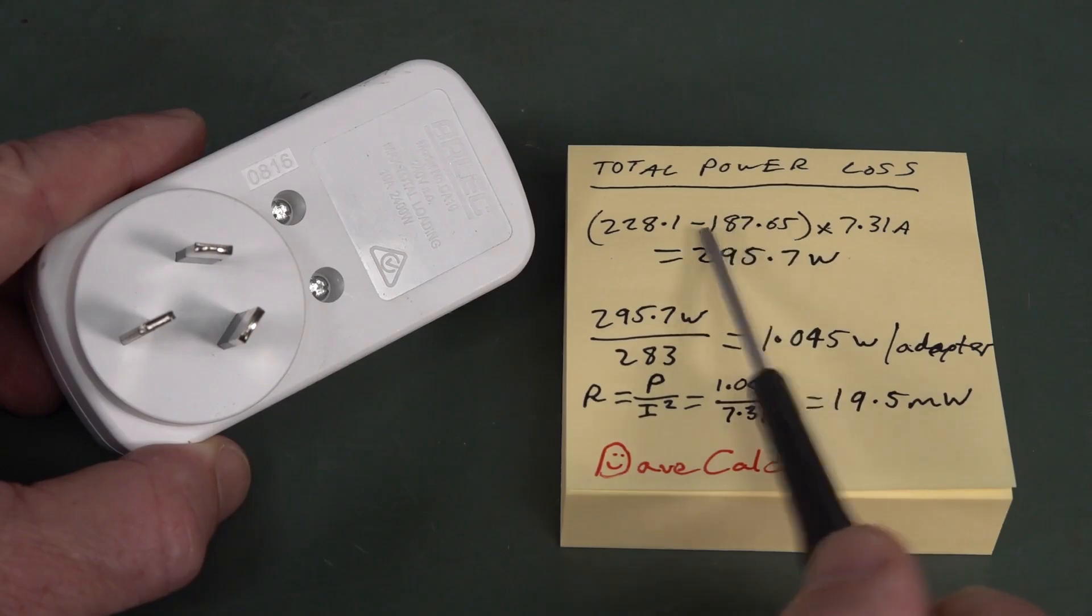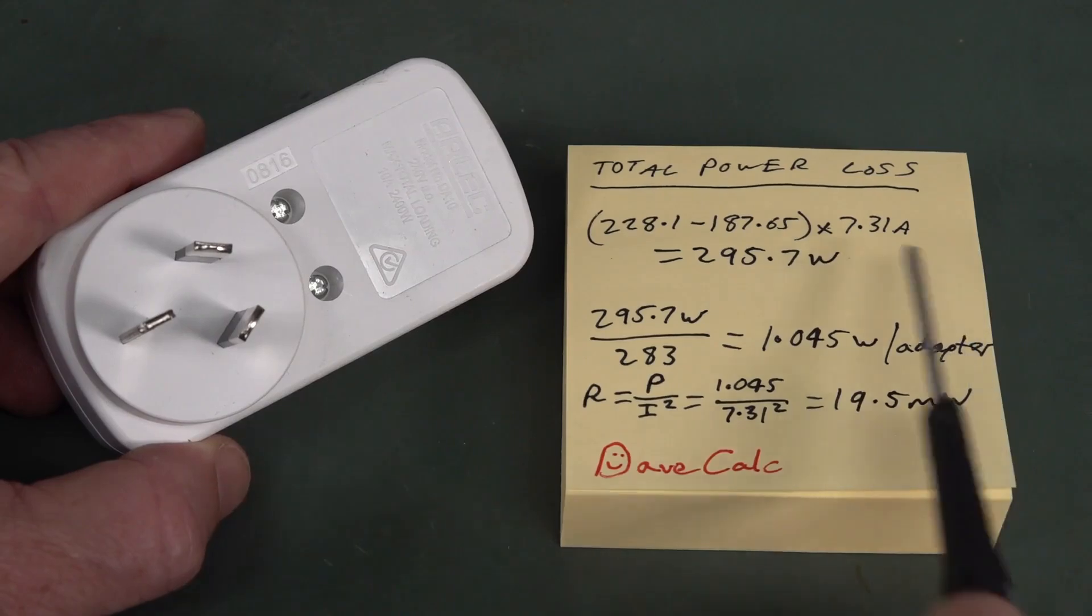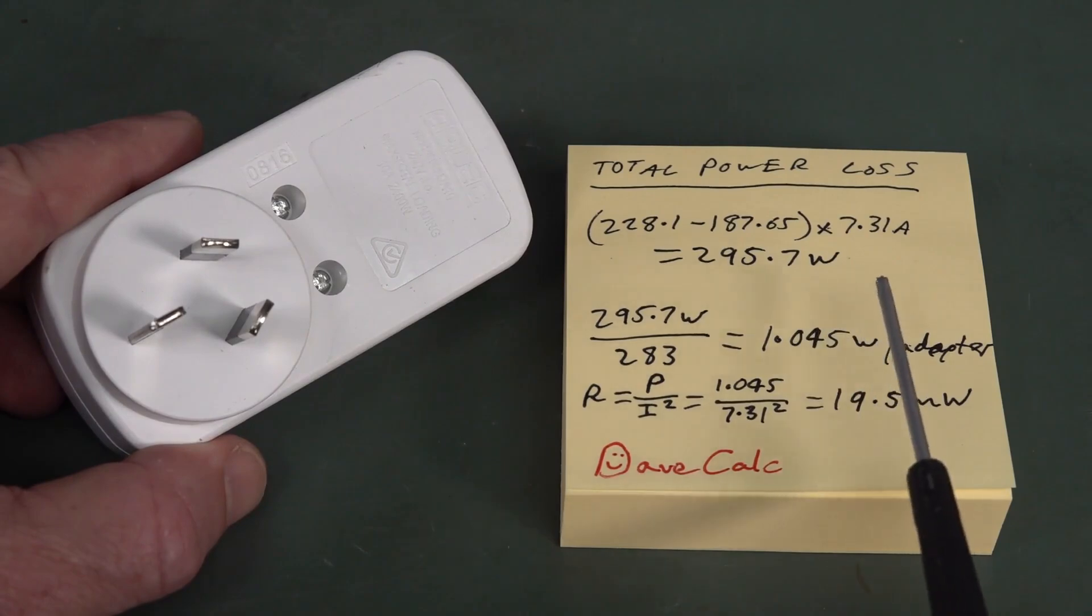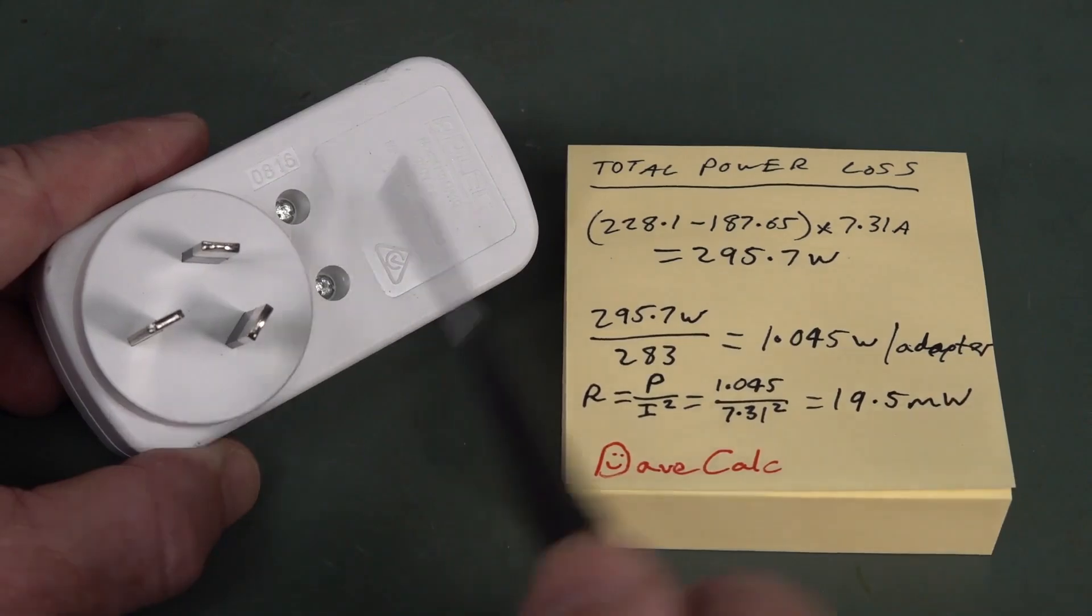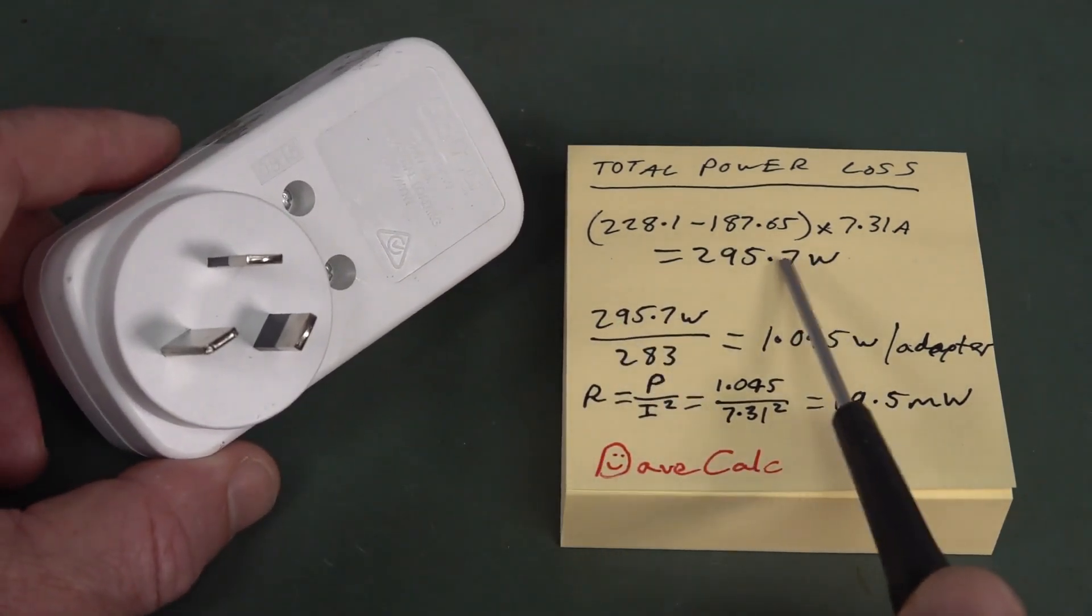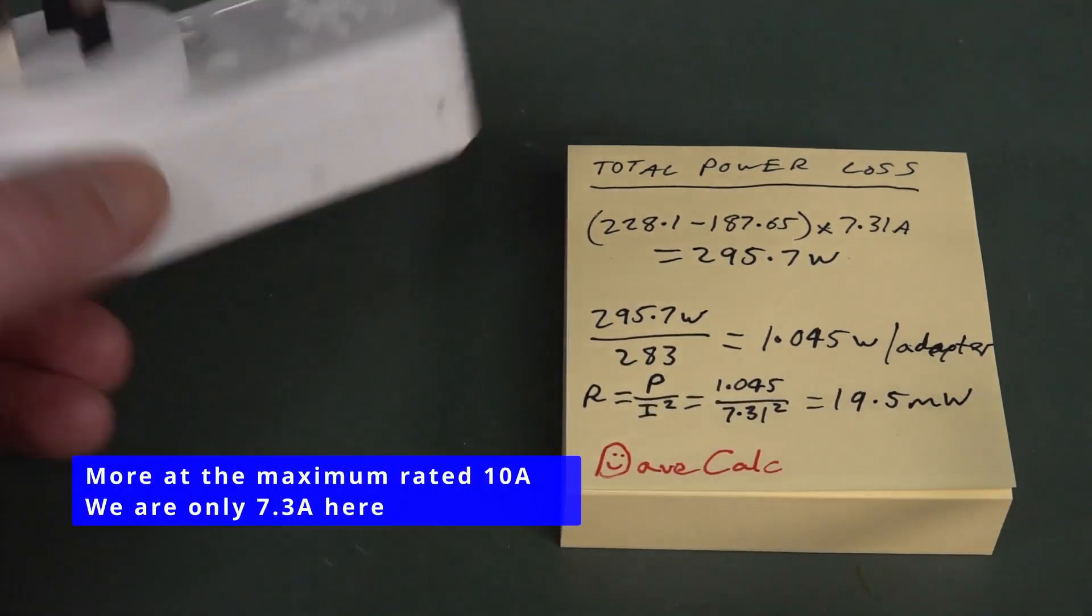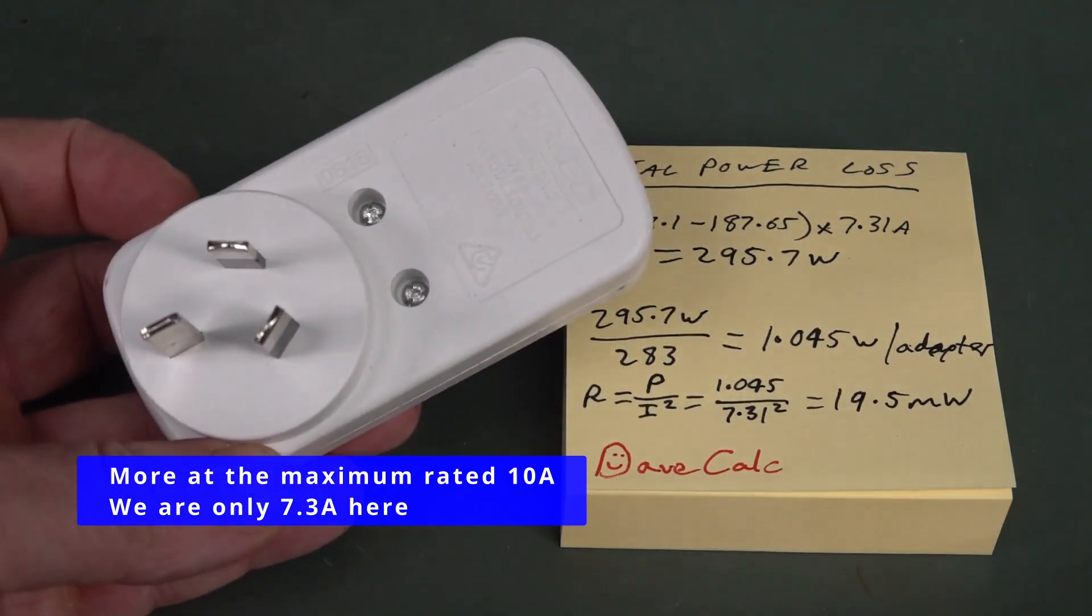Anyway, the total power loss of 283 of these in series is the input voltage. Because it was 240, but then we had some drop across that 20-odd meters of those five extension cords plugged together. So the input voltage to the first one of these was 228.1. So you've got to subtract the output voltage, which was 187.65. And then, that's your voltage drop, and V times I gives you your power, so times 7.31 amps, 295.7 watts.